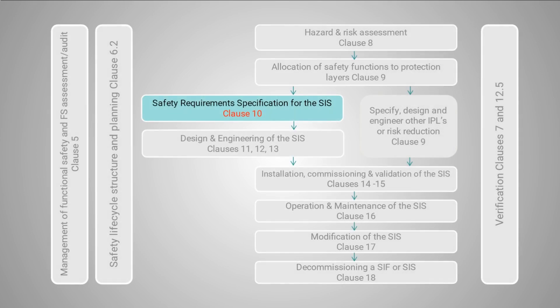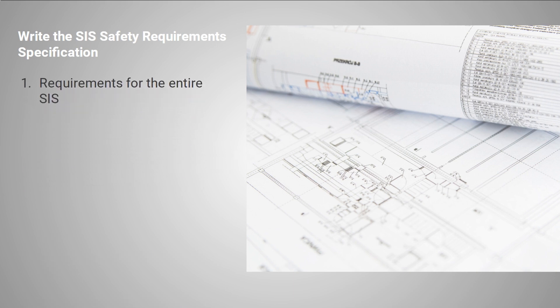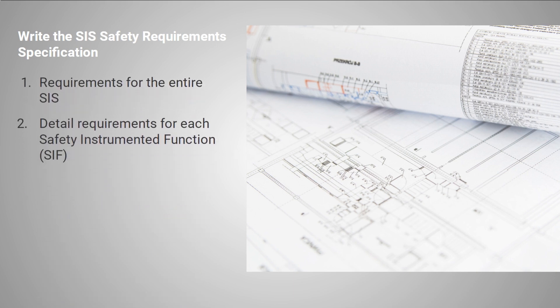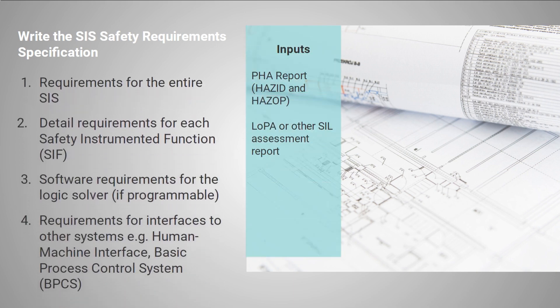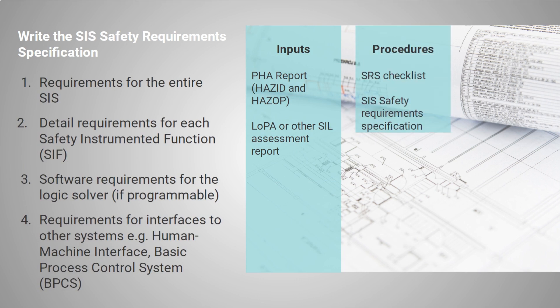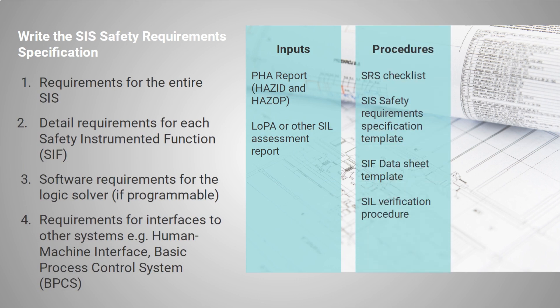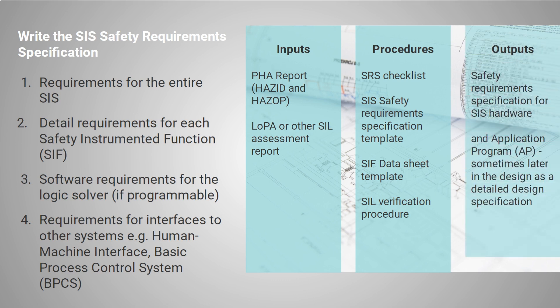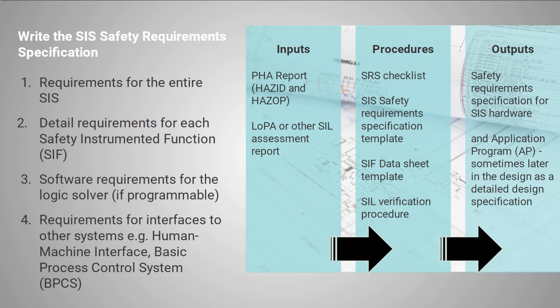Requirements are the blueprint for the SIS design. Functional requirements include what each safety function should do, in terms of what hazard is to be detected and the action to be taken to reach a safe state. Integrity requirements set the standard for the design in terms of safety integrity and system availability.